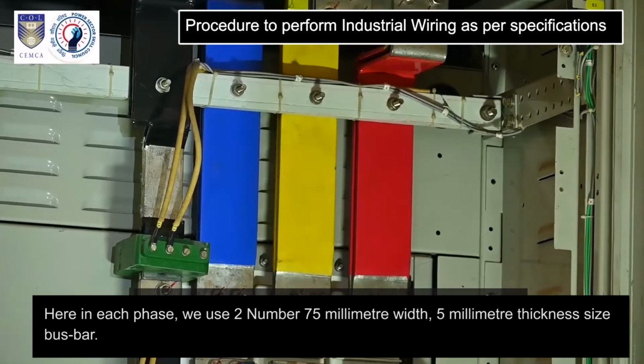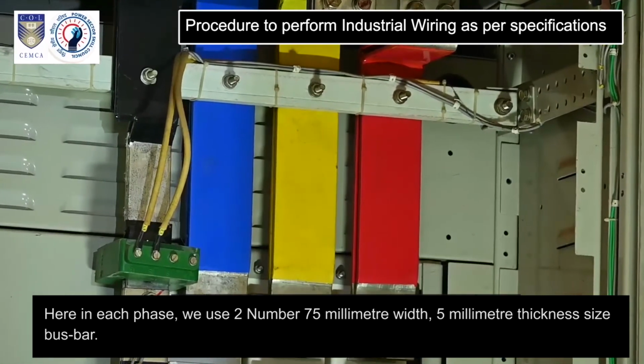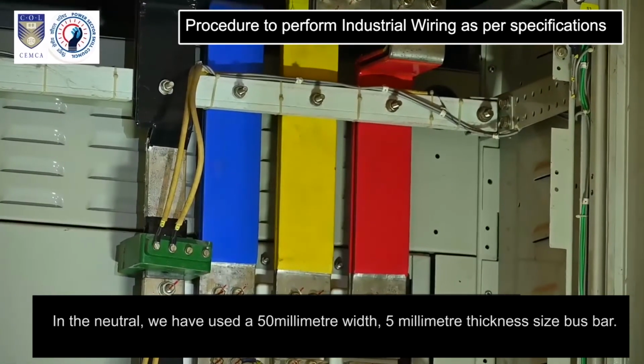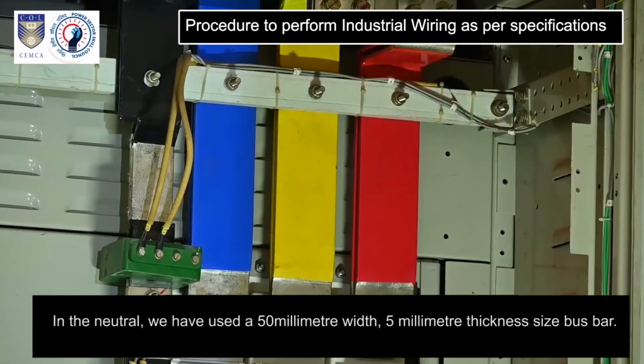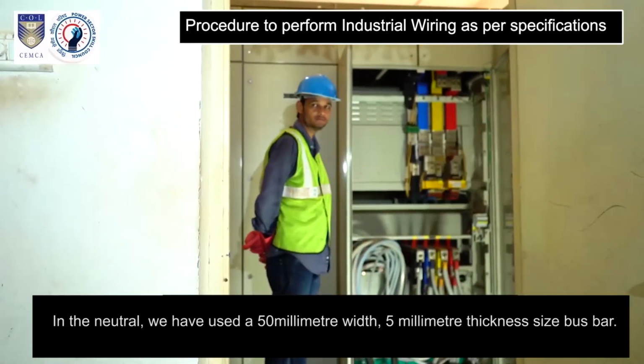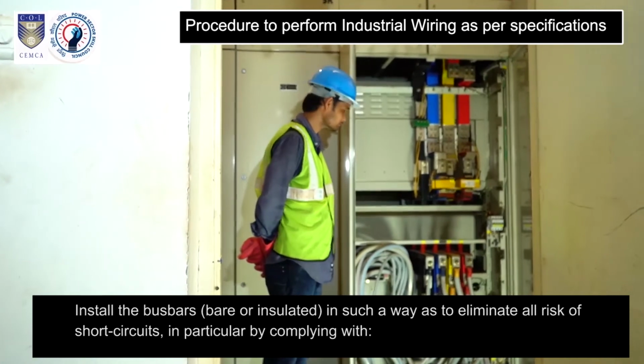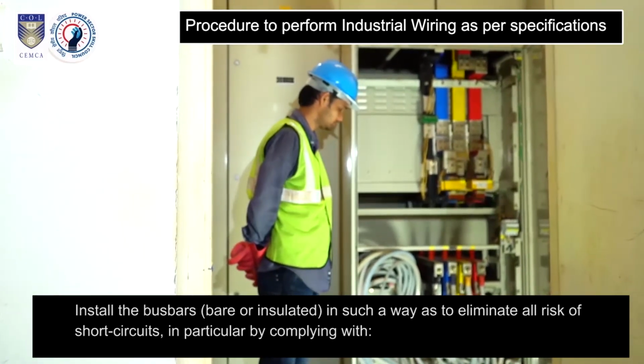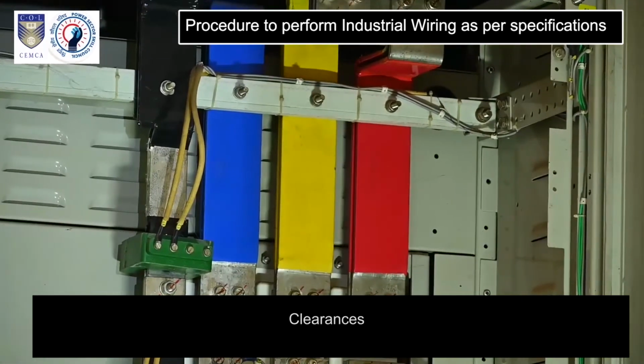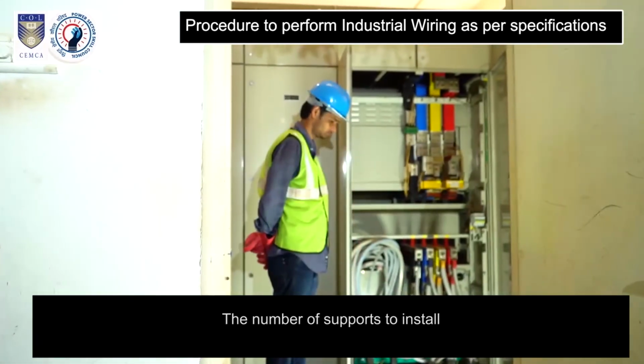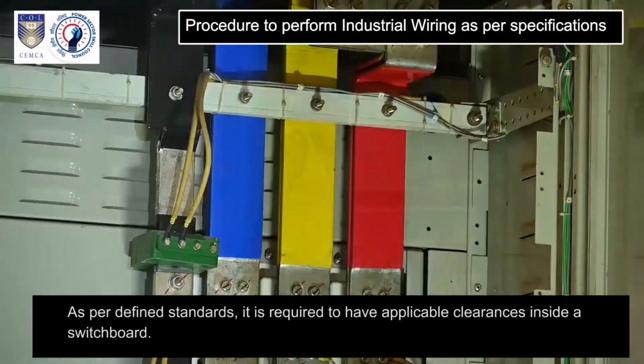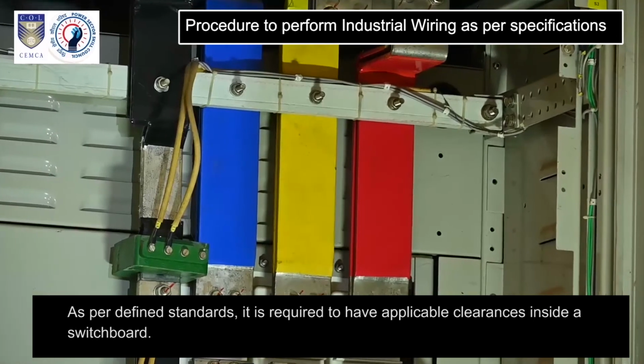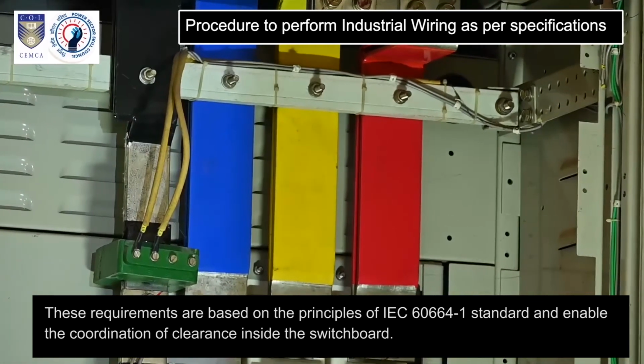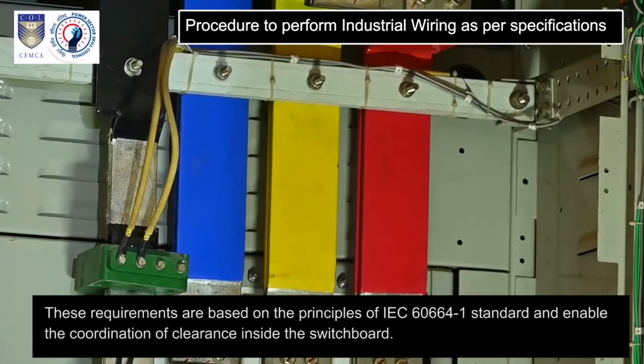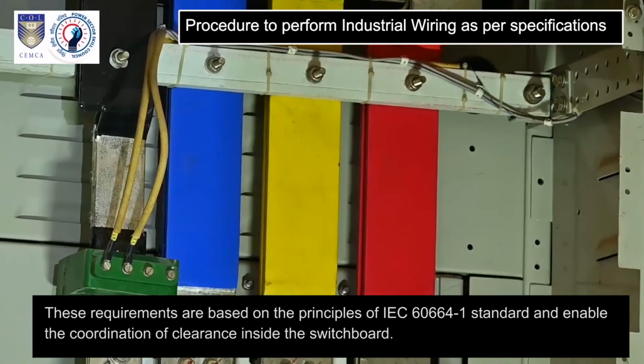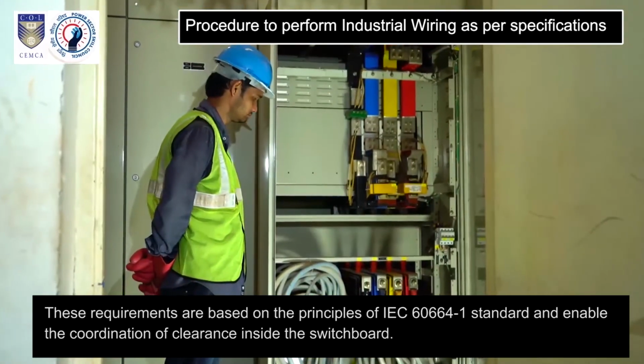Here in each phase, we use two numbers of 75 mm width, 5 mm thickness size busbar. In the neutral, we have used a 50 mm width, 5 mm thickness size busbar. Install the busbars bare or insulated in such a way as to eliminate all risk of short circuits, in particular by complying with clearances, creepage distances, the number of supports to install, the rules for securing these supports. As per defined standards, it is required to have applicable clearances inside a switchboard. These requirements are based on the principles of IEC 60664-1 standard and enable the coordination of clearance inside the switchboard.